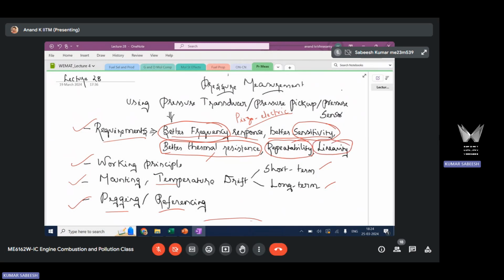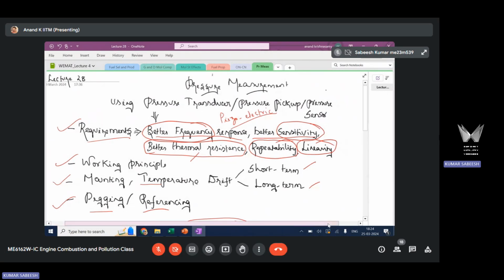Linearity. The sensor output is an electric signal, charge. Just now I showed that for a given change in pressure, this should be linear. What will be the problem if these two are non-linear? Then you will not get any correlation of data, because you have to find the curve equation. So the problem with a non-linear correlation is that you need to extract multiple constants. If the output and the input have a non-linear correlation, it is going to create problems in terms of calibrating the sensor. We need to have a linear relationship.